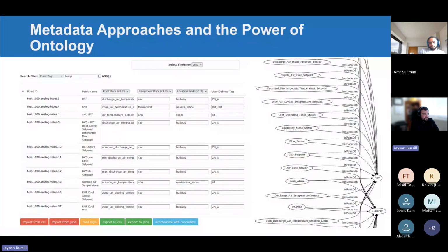A few years ago, I built a basic JavaScript interface where you could take point IDs and point names and read those in from a BACnet device, then start to put brick tags on things. This was useful because it interacted directly with the BACnet tags property, so you could embed this within BACnet data on a building automation controller. Do I think this is the best way to do it now? I don't know, but it's a good way to access the data, potentially from a third-party system that can read BACnet and route through different protocols and gateways.